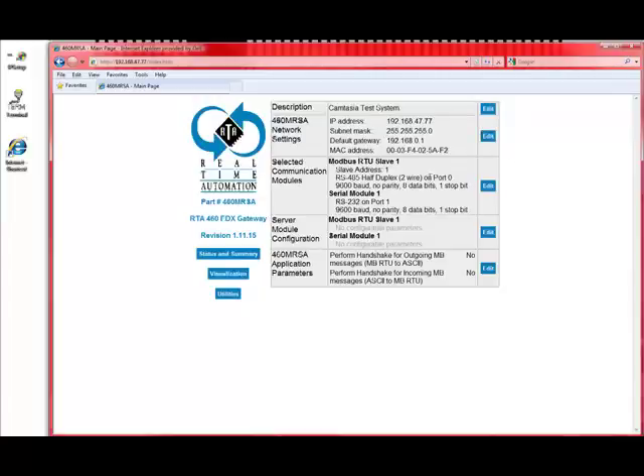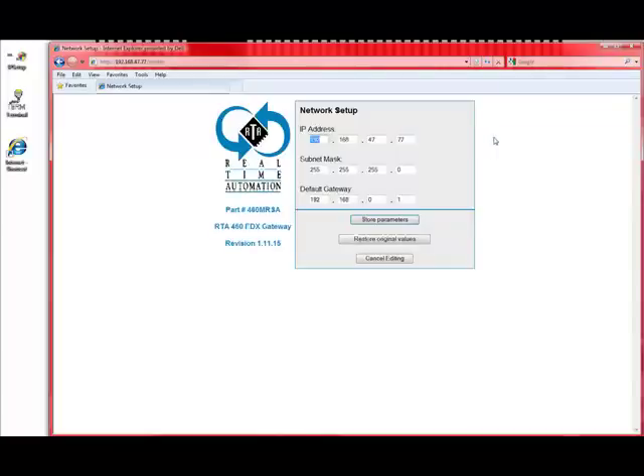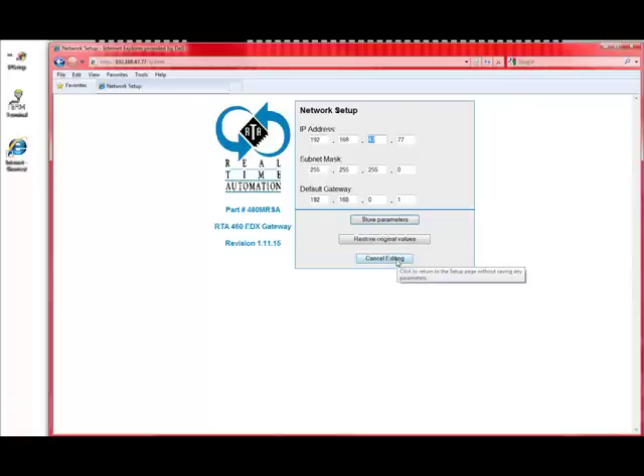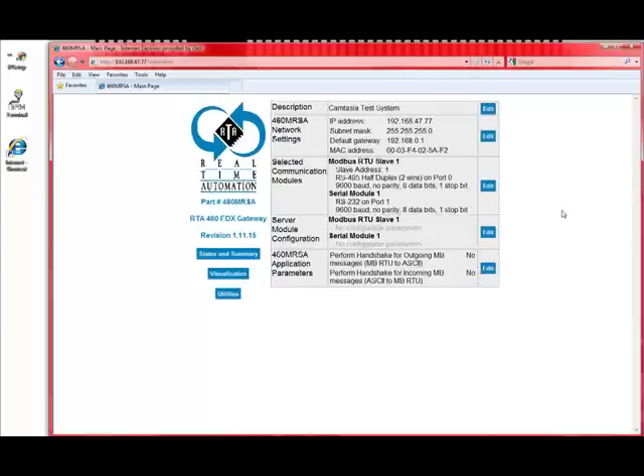The second thing on the panel here that we can modify is the network setup. That's essentially just the address of the unit. The current address is 192.168.47.77, and we're free to go in and modify this to whatever we want. When you get the unit, it's going to be 192.168.0.100. You'll need to set your PC up to be on that same subnet, 192.168.0.1, for example. And then you'll be able to talk with using a crossover cable directly to this or using a switch. So I'm going to cancel this edit because we don't need to change the IP address at this point in time.